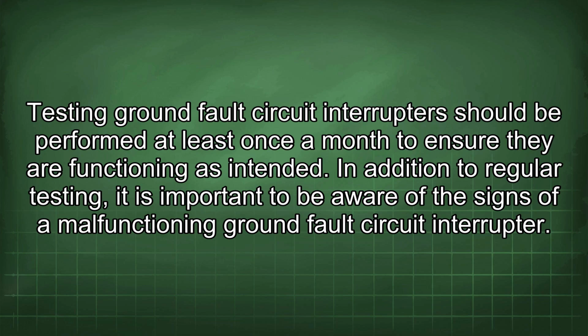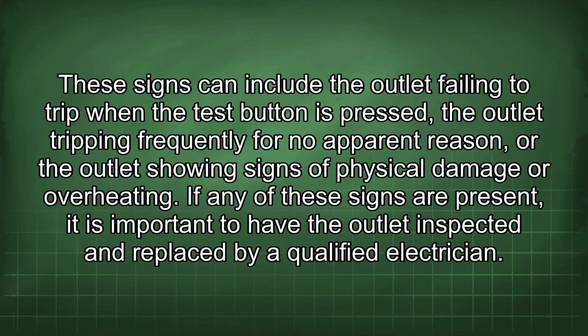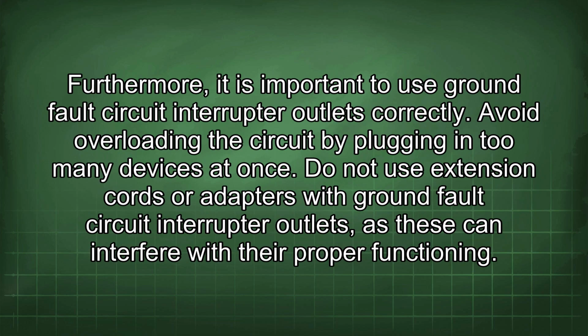In addition to regular testing, it is important to be aware of the signs of a malfunctioning ground fault circuit interrupter. These signs can include the outlet failing to trip when the test button is pressed, the outlet tripping frequently for no apparent reason, or the outlet showing signs of physical damage or overheating. If any of these signs are present, it is important to have the outlet inspected and replaced by a qualified electrician.